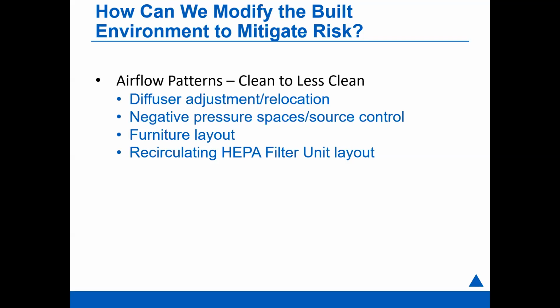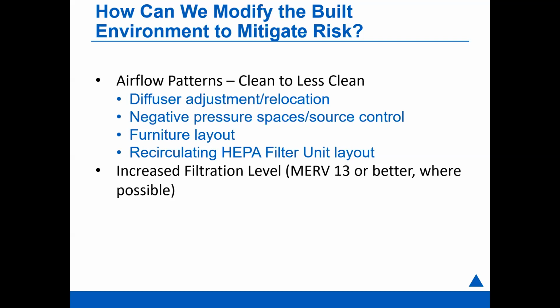And certainly recirculating HEPA filters inside buildings. There's also the opportunity to increase filtration level if you have a home or an office where the filtration level isn't very great. The ASHRAE Epidemic Task Force is recommending upgrading to a MERV 13 or better wherever possible. You have to look at your HVAC system, see if it's compatible. But good quality MERV 13 filters can, in some cases, have less pressure drop across them than a poor quality MERV 8 or MERV 11 filter. So you may be able to find a filter to replace that won't tax your fan horsepower capacity beyond what it's capable of doing.